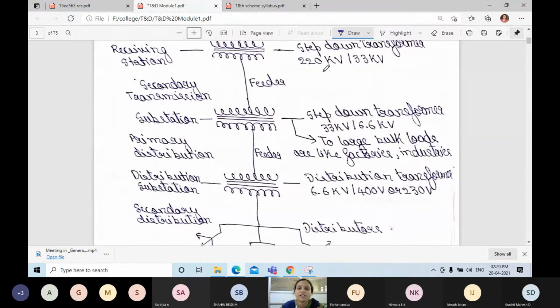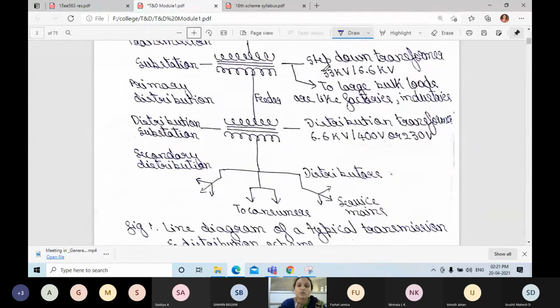Next, coming to primary distribution. Here, from 33 kV to 6.6 kV is transmission, and next, primary distribution is from 6.6 kV to 400 or 230 volts. We will step down continuously from one voltage level to another, till 230 volts or 400 volts. We, the consumers, use 230 or 400. The supply will be 230, or for some particular loads 400.